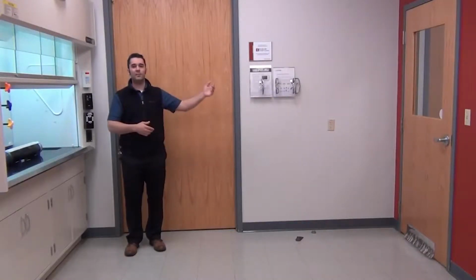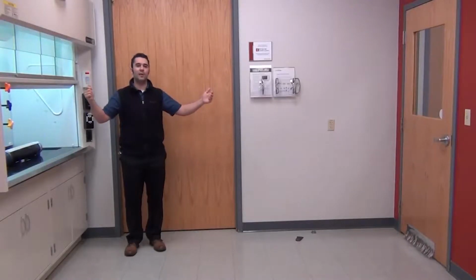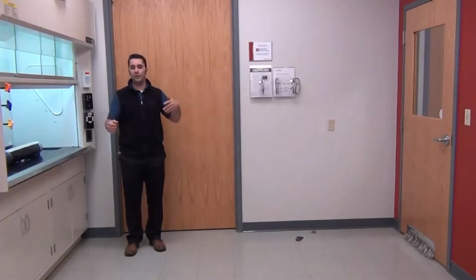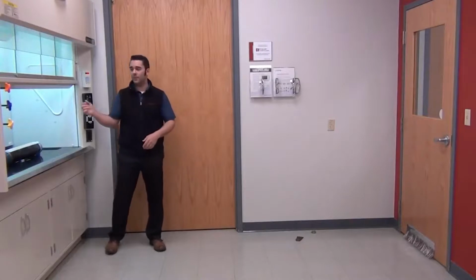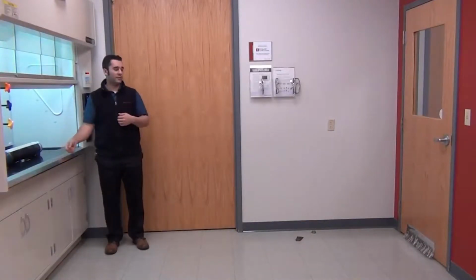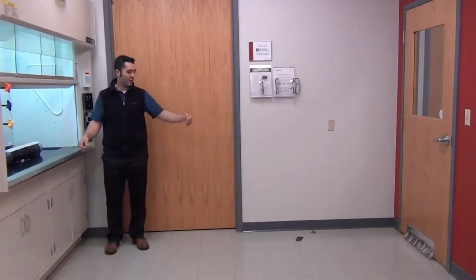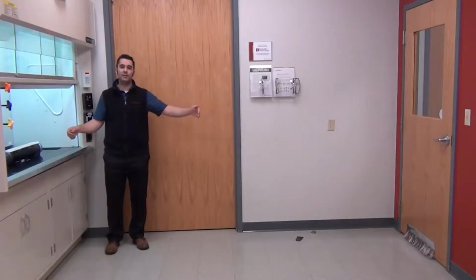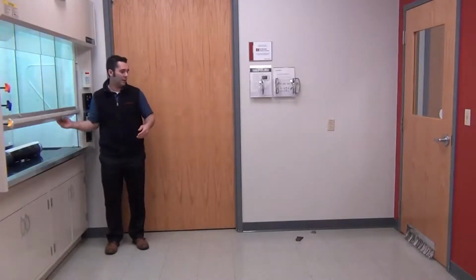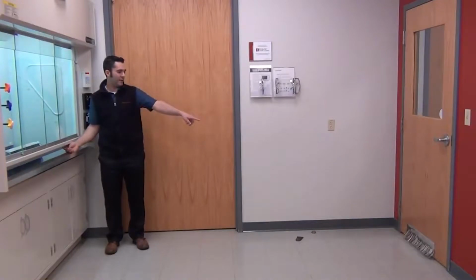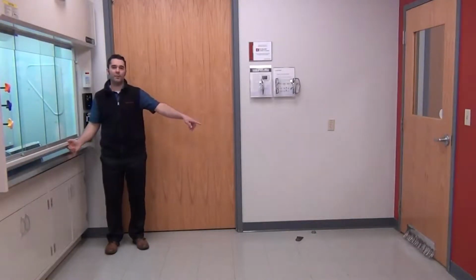So if I had an issue happen in one of the other rooms at the same time I open this hood, there's a possibility that I'm going to get cross-contamination. Now again, conversely, when I close this hood, if you watch the hula skirt, it's actually going to go dead and slightly positive and then come back in. So there you see, my room just went positive for a couple of seconds.